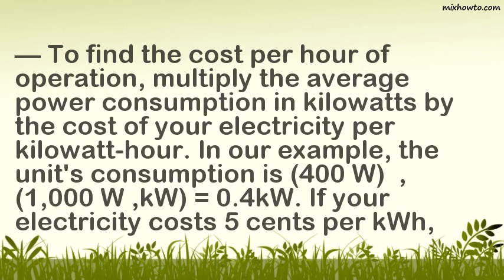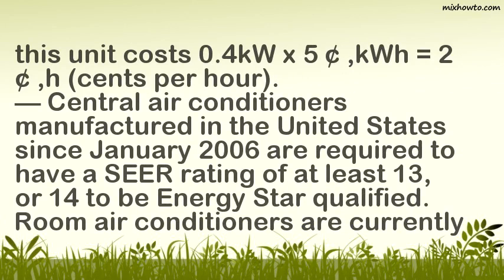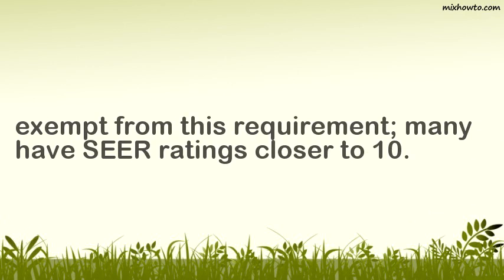To find the cost per hour of operation, multiply the average power consumption in kilowatts by the cost of your electricity per kilowatt-hour. In our example, the unit's consumption is 400 W ÷ 1,000 W/kW = 0.4 kilowatts. If your electricity costs 5 cents per kWh, this unit costs 0.4 kW × 5 cents/kWh = 2 cents per hour. Central air conditioners manufactured in the United States since January 2006 are required to have a SEER rating of at least 13, or 14 to be ENERGY STAR qualified. Room air conditioners are currently exempt from this requirement. Many have SEER ratings closer to 10.